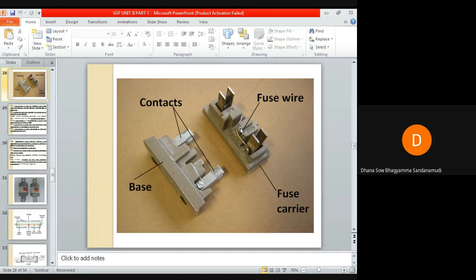So when a fault occurs, the fuse element is blown out. Means the melting point of this fusing element, the tinned copper wire element, is reached whenever a fault occurs, whenever excessive current is there in the circuit in which this fuse is connected. So it reaches its melting point and just blows out and the circuit is interrupted. As soon as the circuit is interrupted, the fuse carrier is taken out from the base and the fusing element is replaced with a new one, and after replacing it, the fuse carrier is reinserted into the base to restore the supply.